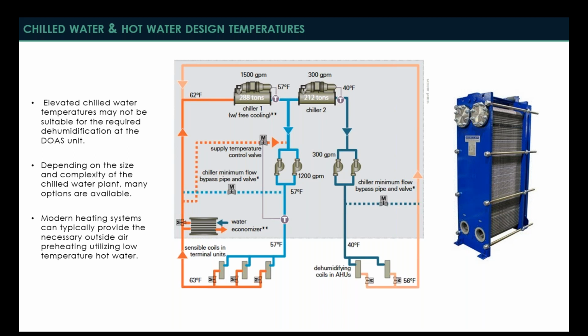So depending on the size and the complexity of your chilled water plant, there are a lot of different options. Sometimes on a very small plant, you'll simply put in a heat exchanger, like is shown in the image on the right, and create a separate elevated temperature chilled water loop for your radiant system. But on bigger systems that have multiple chillers, there are other very unique and interesting options that can maximize the efficiency of that plant while simultaneously creating the two temperatures of water that you need. So it's something that just needs to be paid attention to in the design of these systems.